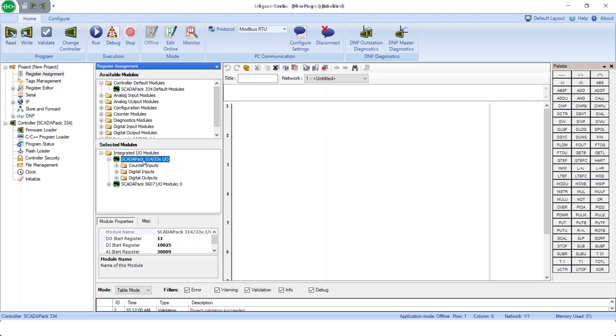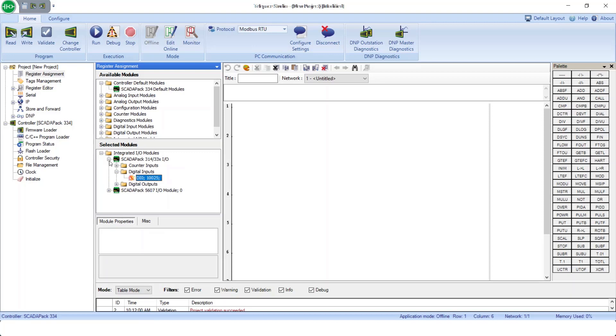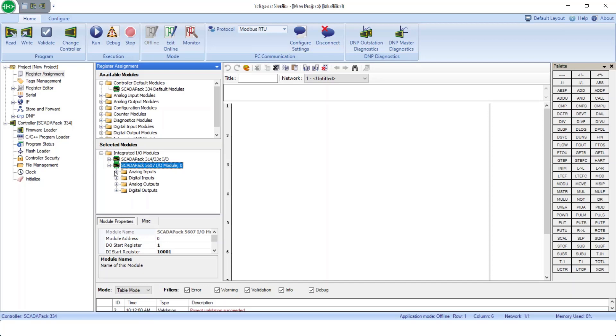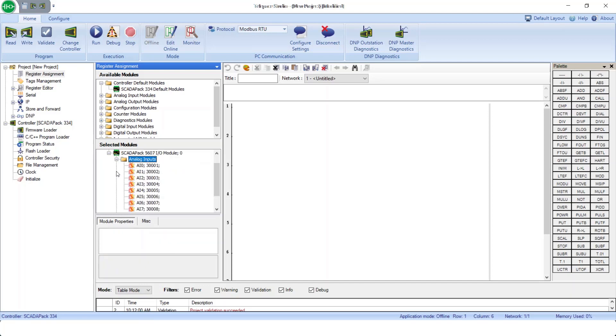The controller board has certain I/O tied to Modbus. And the lower board, the 5607 board, also has its I/O. Here I can have a look at the analogs in, and I can see analog in 0, for example, is tied to Modbus register 30001.